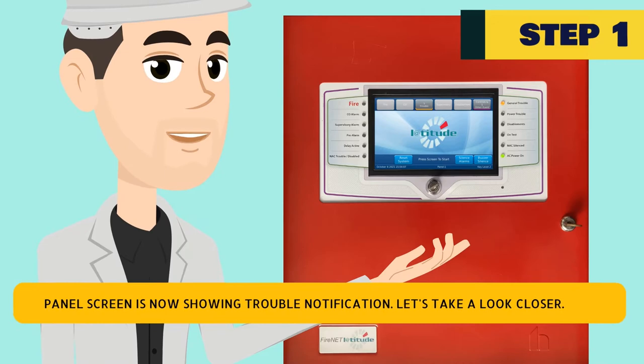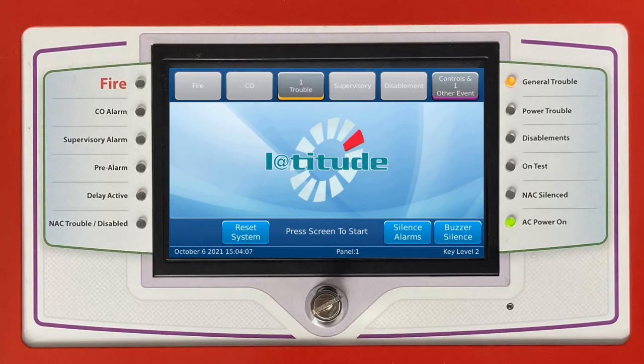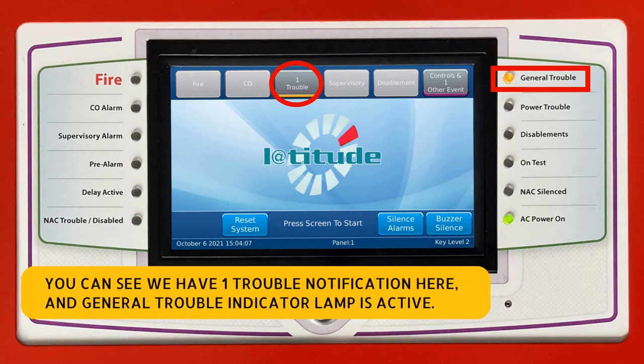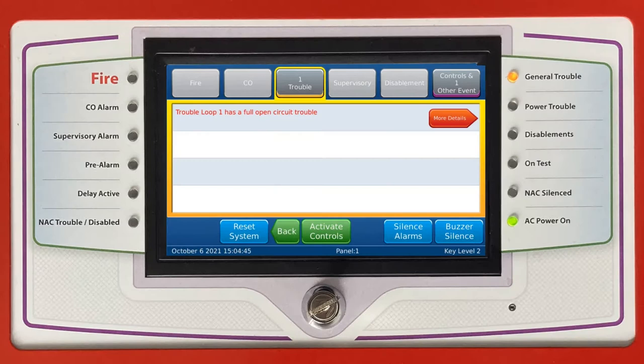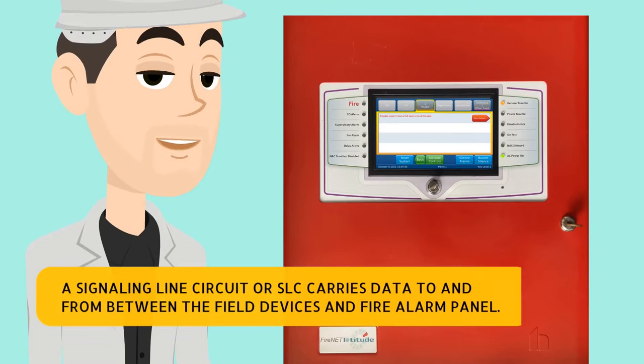The panel screen is now showing a trouble notification. Let's take a closer look. You can see we have one trouble notification here, and the general trouble indicator lamp is active. Now press the trouble tab. Trouble loop 1 has a full open circuit trouble.